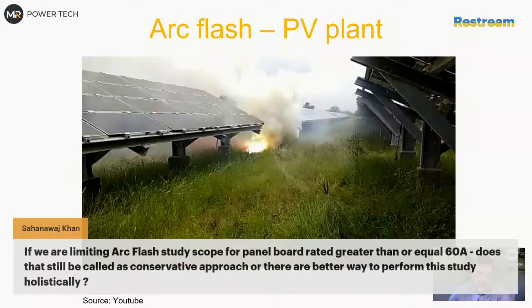So what I did, and I know a lot of people are doing it a similar way, we said we go down to 60, 63 amp protection level in the first phase. Usually if I identify panels on site which are like 50, 40 amp, I still include them in the study just to have all the panels, not machines, but all the panels. So this is a very good first approach to a site.